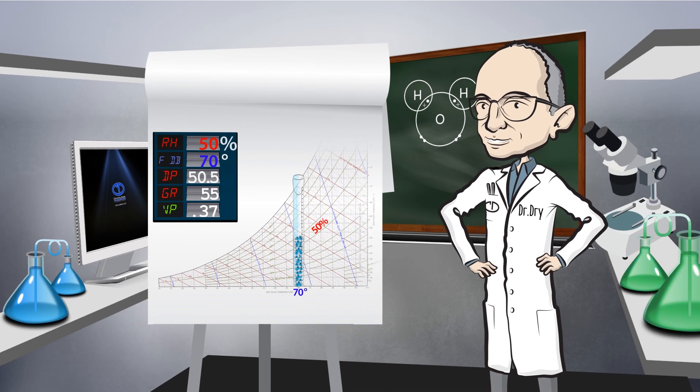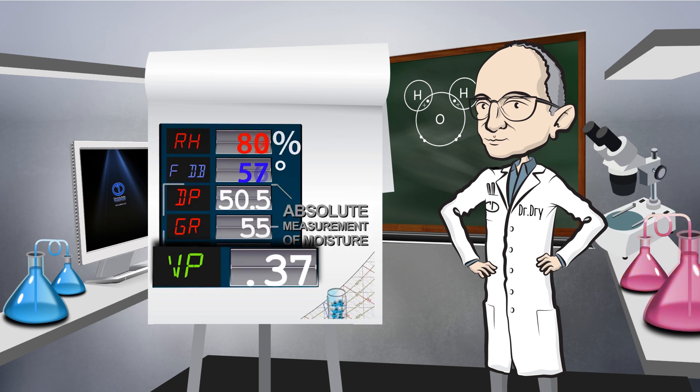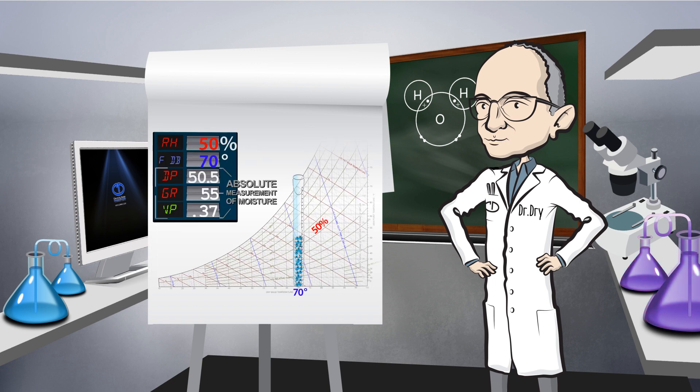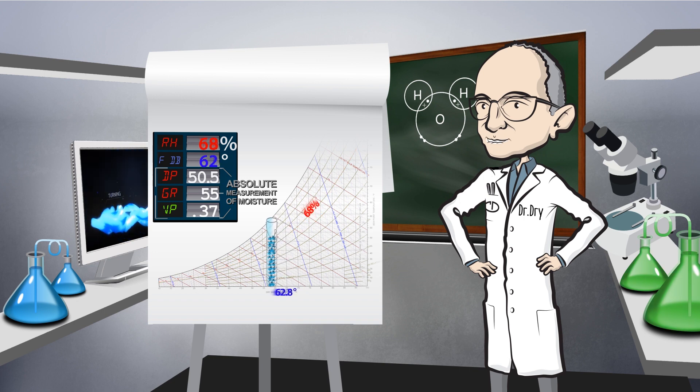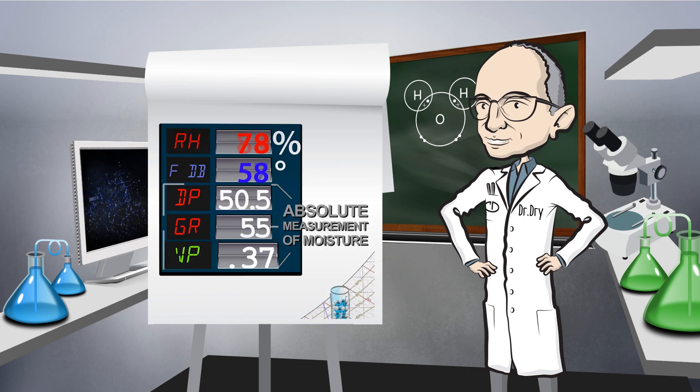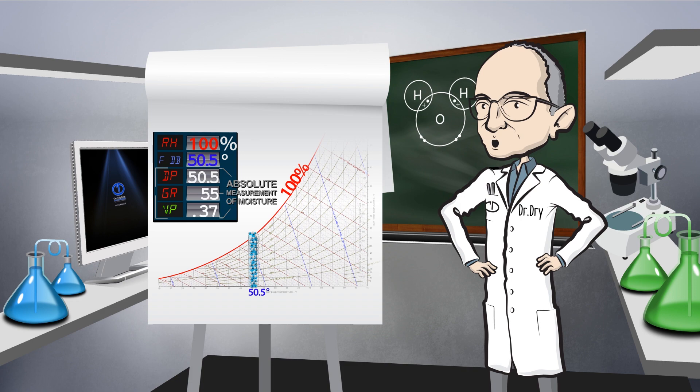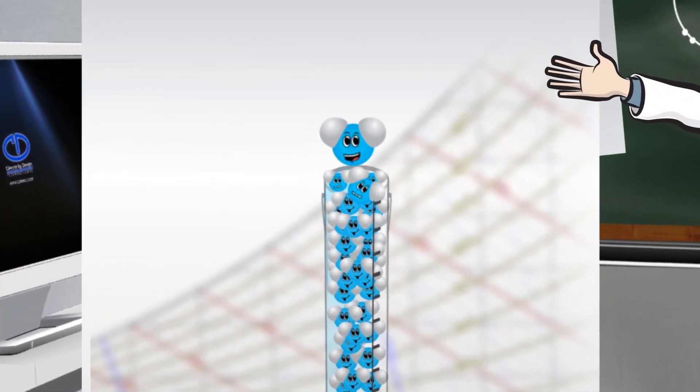In our subject today, moisture in air measured as vapor pressure. Vapor pressure is a measurement of the partial pressure or that part of the pressure of the moisture in the air. It is an absolute measurement of moisture, meaning it does not change with a temperature increase or decrease unless, of course, you get to the point of condensation.